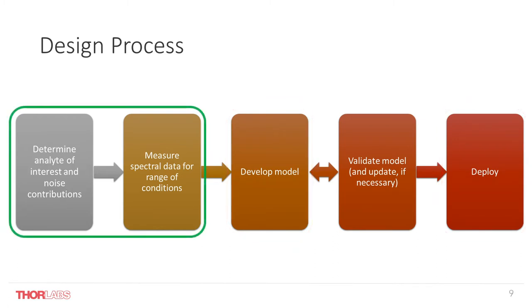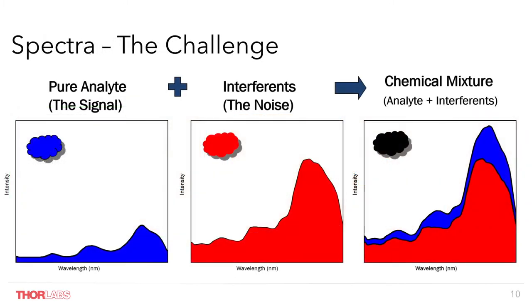In the case of this demo, after defining our desired oils to measure, we started with spectral measurements on all the oils we showed earlier. Before we look at the actual spectra, let's discuss a common challenge encountered when performing spectral measurements of any complex matrix like the one we have here. Quite often, we are not measuring our pure analyte alone. Instead, we are given a matrix which contains some combination of our analyte of interest as well as interference. In our design process, these interferences are treated as noise and baked into our overall model and system design.